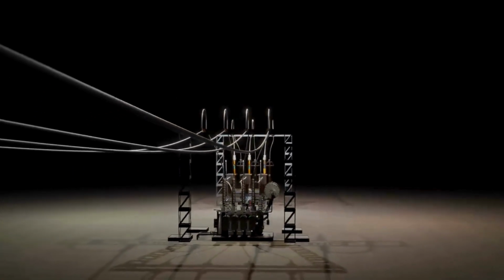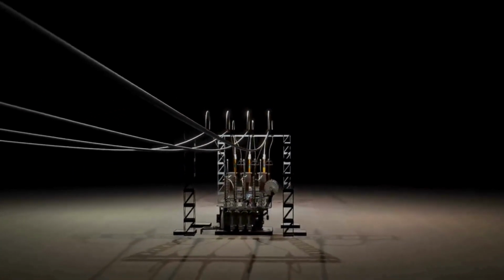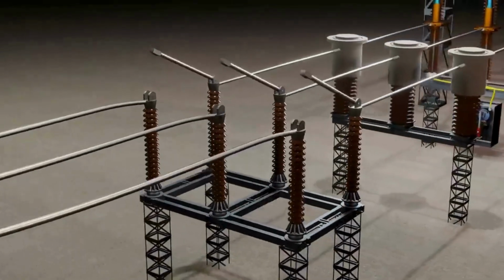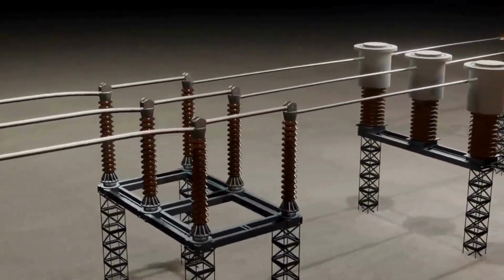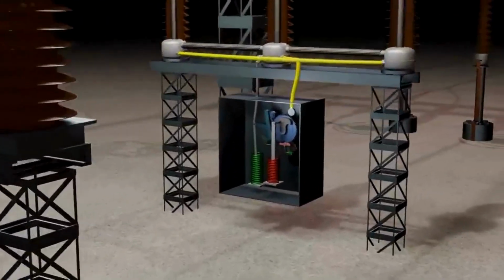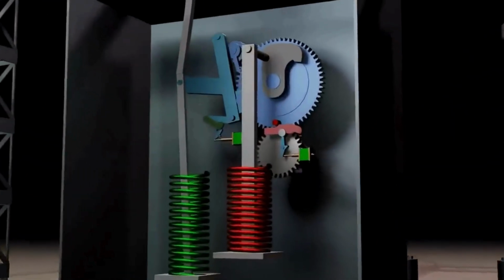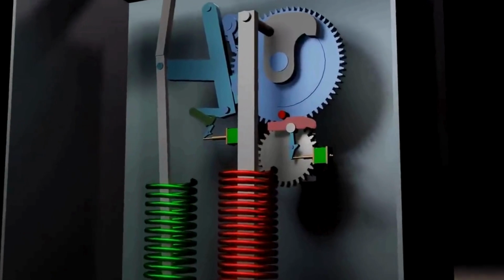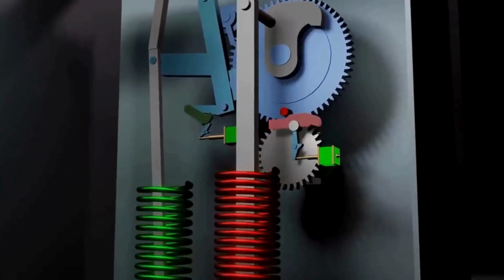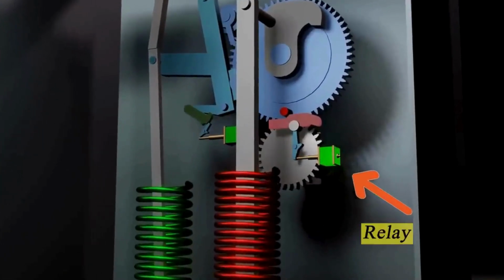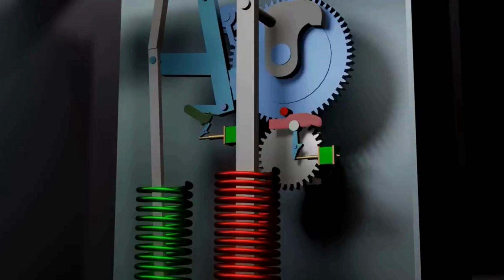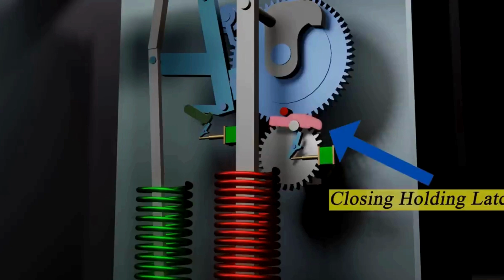The line is currently open and one spring is also unloaded, so there is one more relay here to close the line. This relay is activated by the control as soon as it is free. The force of the closing spring is coming on this cam, which is still loaded, and it rotates this cam at a speed. The cam pin will apply force on the lever and the lever will load the spring on the side again, so that the line will be closed again.